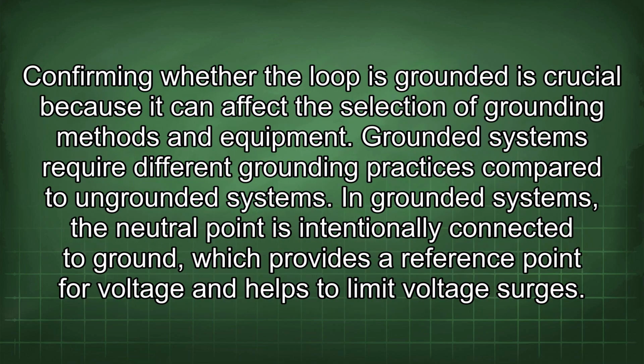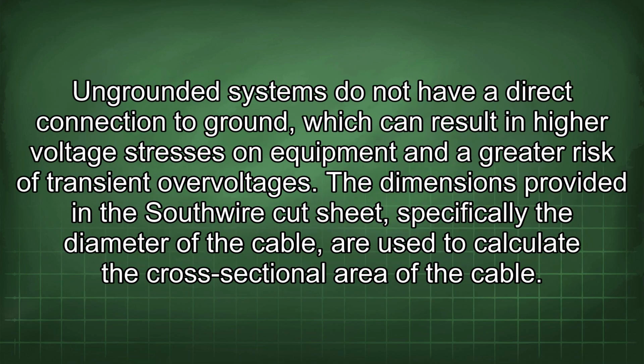Confirming whether the loop is grounded is crucial because it can affect the selection of grounding methods and equipment. Grounded systems require different grounding practices compared to ungrounded systems. In grounded systems, the neutral point is intentionally connected to ground, which provides a reference point for voltage and helps to limit voltage surges. Ungrounded systems do not have a direct connection to ground, which can result in higher voltage stresses on equipment and a greater risk of transient overvoltages.